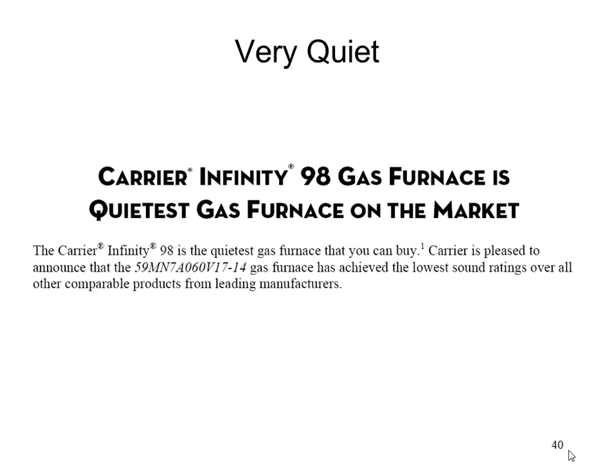Real quick, we have a question from Brian asking, does it require a special stat? There's kind of two answers to that. Technically, no. There is a little jumper you can cut on this guy, and then this furnace could run on a regular thermostat if you wanted it to. However, you're going to lose all these modulating benefits that we're talking about. So to really get the full benefits of the furnace, you have to have the Infinity Carrier or the Evolution Bryant communicating stat on the wall.